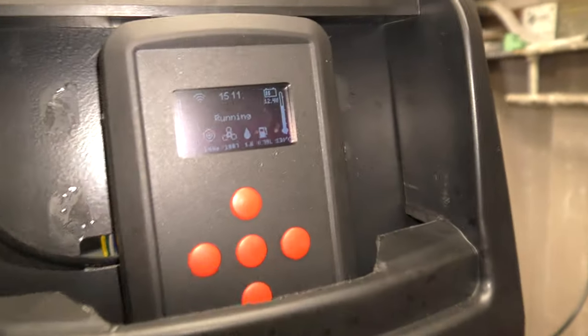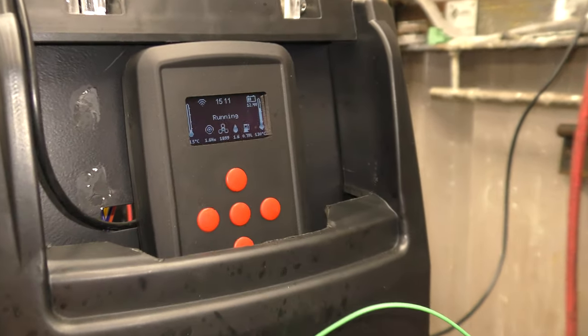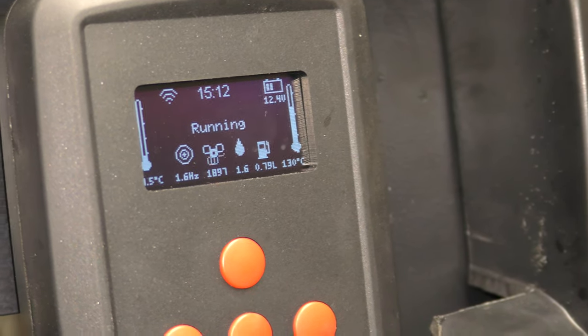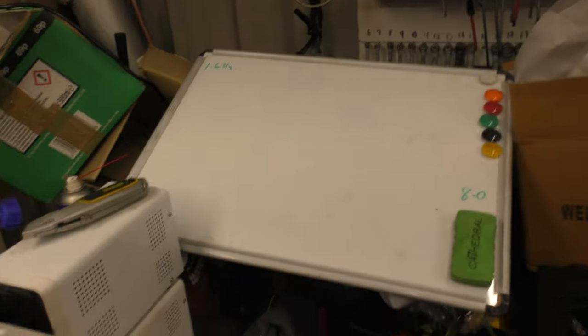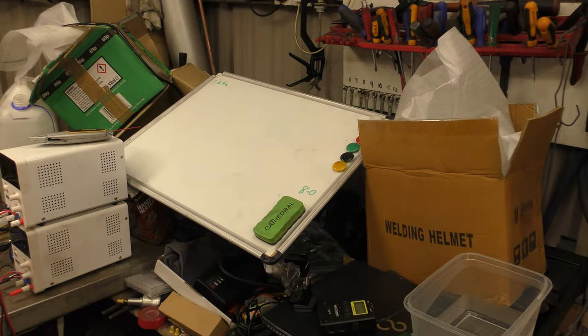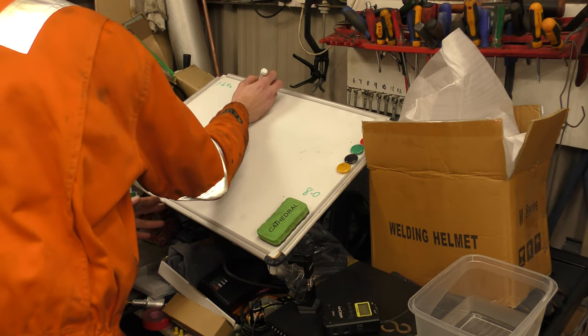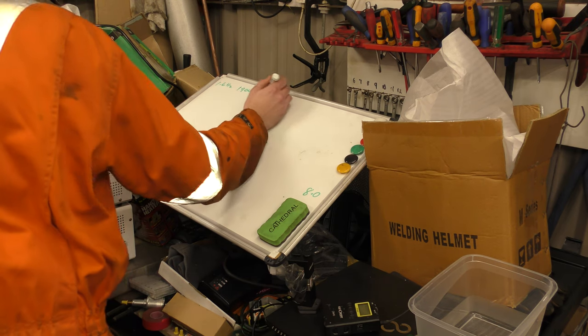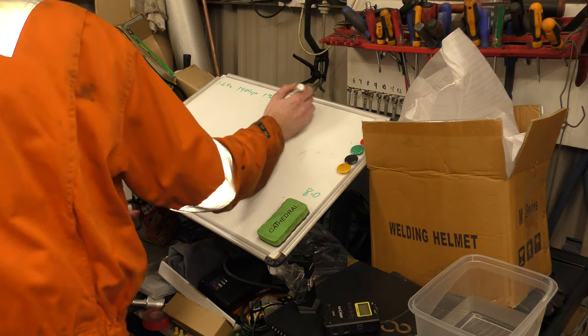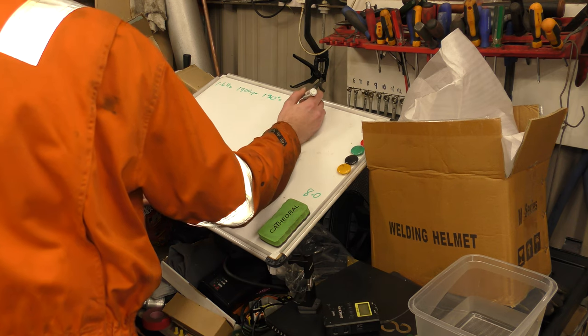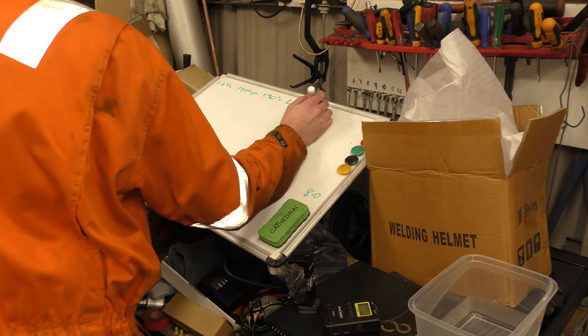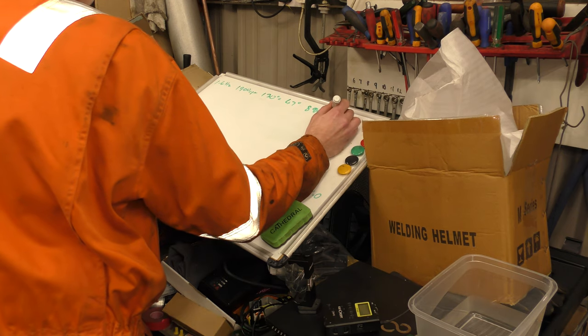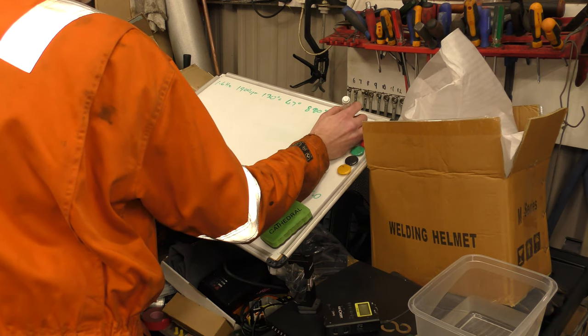And we have a housing temperature of 130 degrees, 1.6 hertz and 1900 RPM. So I should write all this down on the whiteboard. 1.6 hertz, 1900 RPM, housing temperature of 130 degrees, air output of 47 degrees, burn chamber temperature of 890 degrees, and a carbon monoxide reading of 25 parts per million.